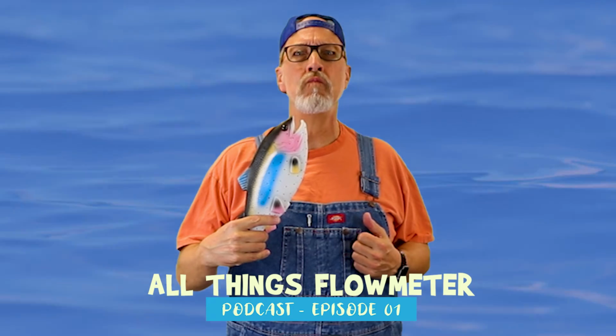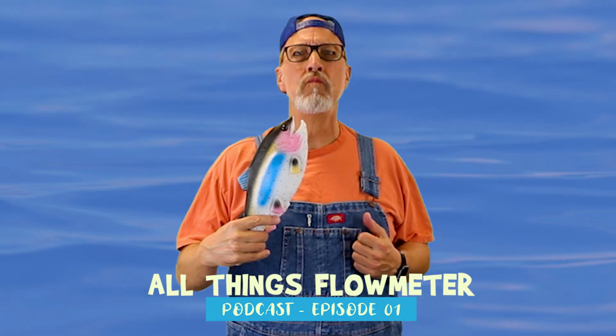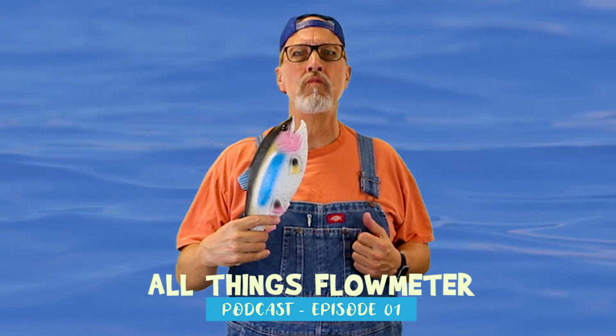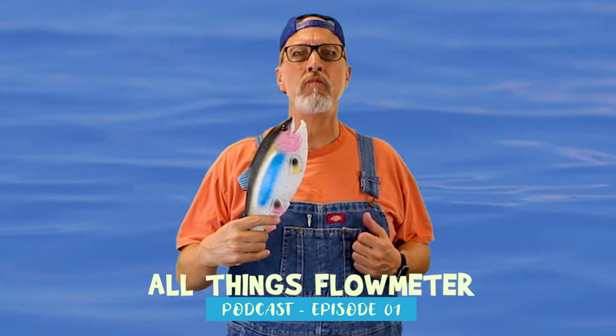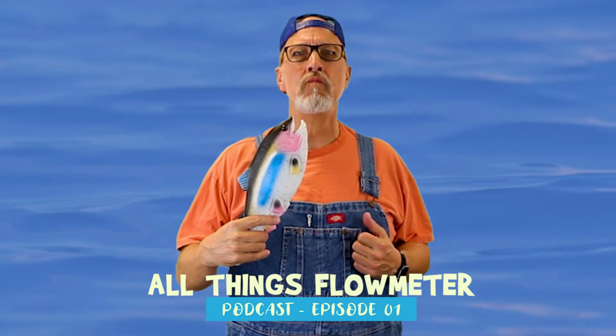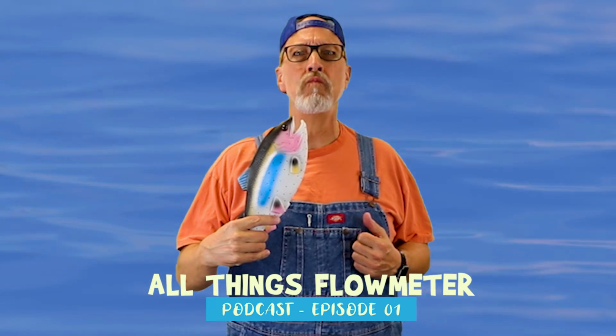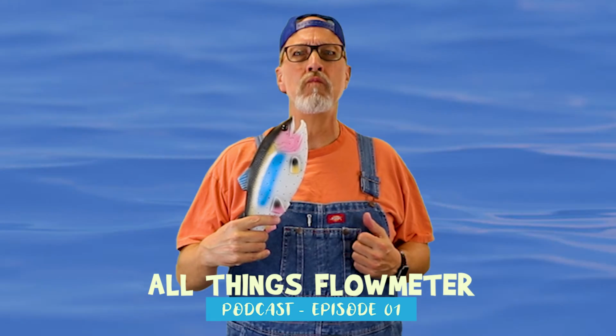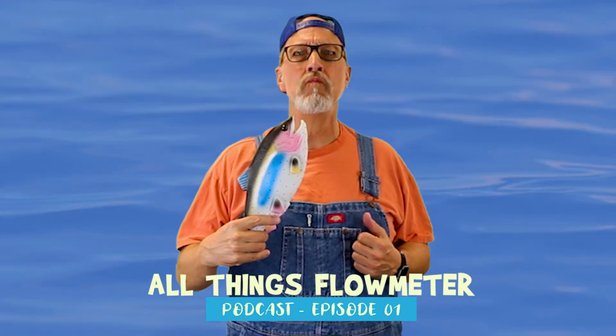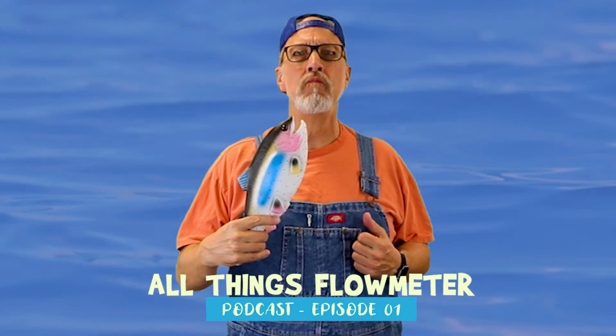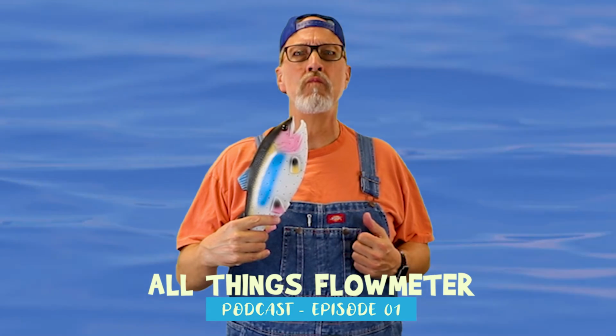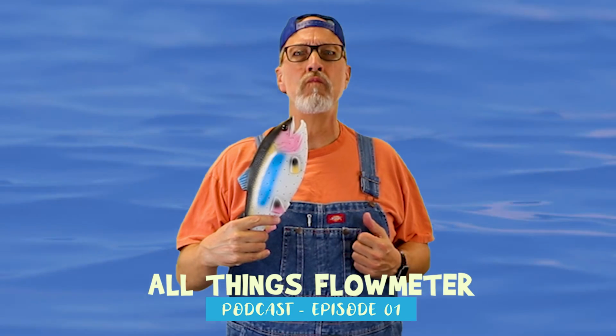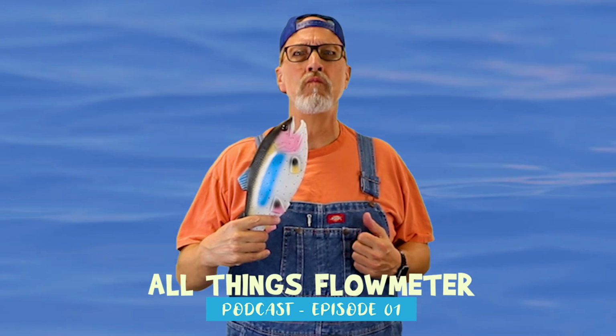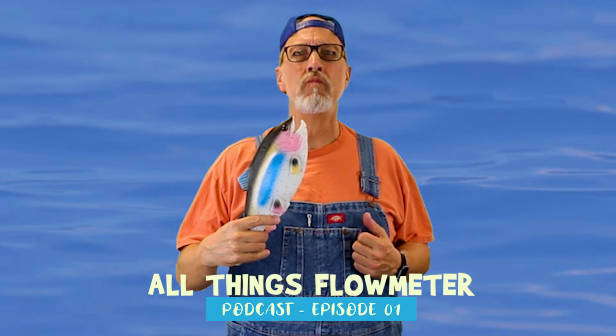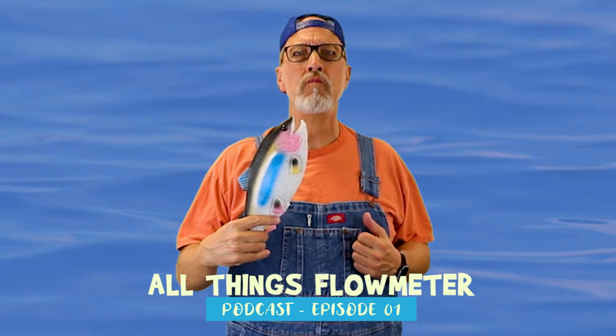So when we go into the field there, you have to have credibility. And I did say attitude actually plays a role. When we go in the field to test another meter, we'll say, this meter's right, damn it. And here's our calibration certificate. And sometimes it takes an authoritative nature to actually present it. And again, if they don't like it, they can pull that flow meter and send it to a laboratory and do their own flow testing, which in many cases is not a practical thing to do. So that's why we come to the field, or rent, or they have their own equipment to go to the field to validate the test equipment.